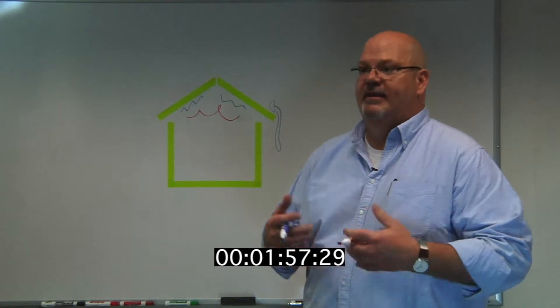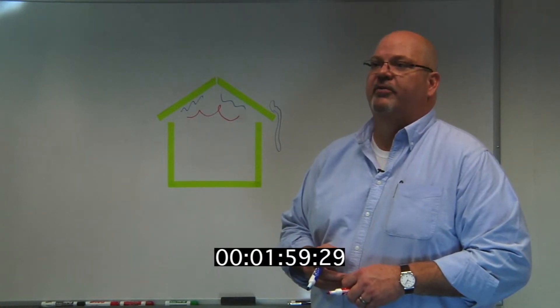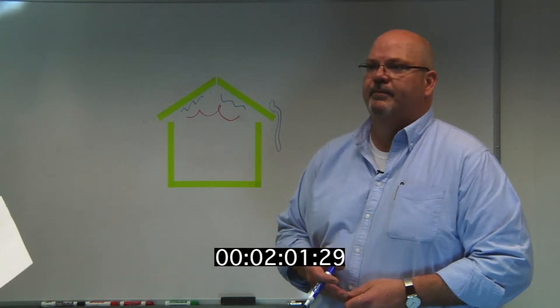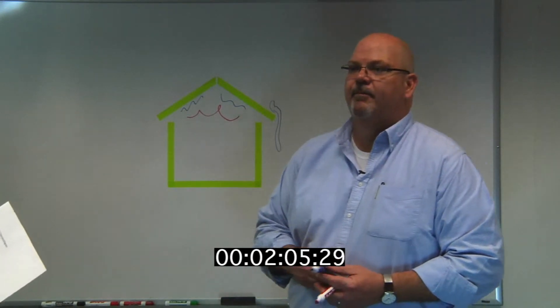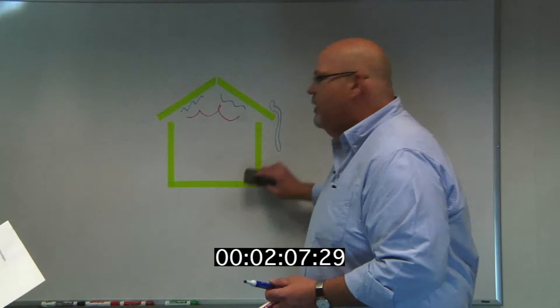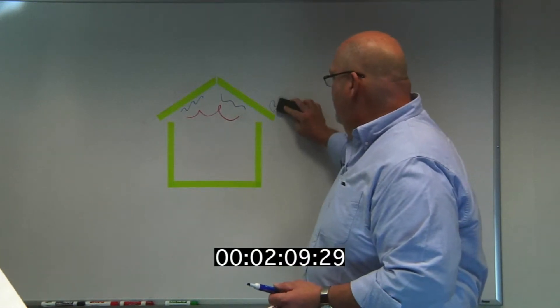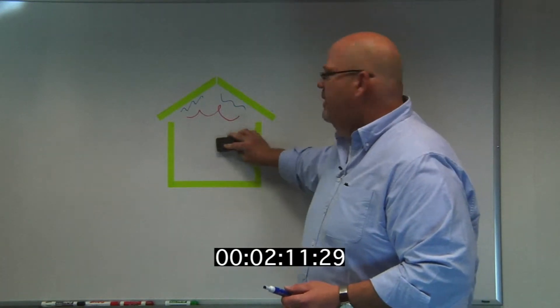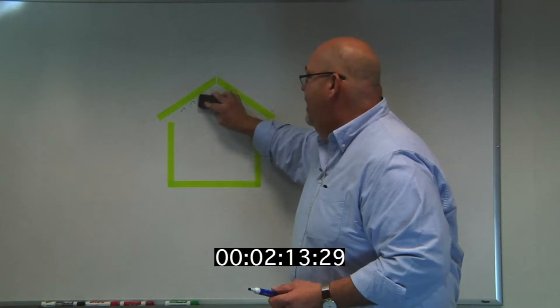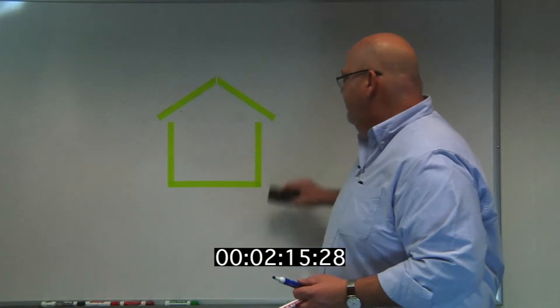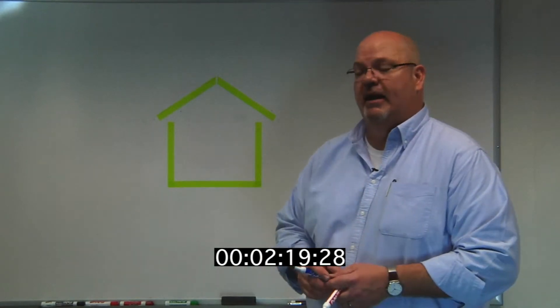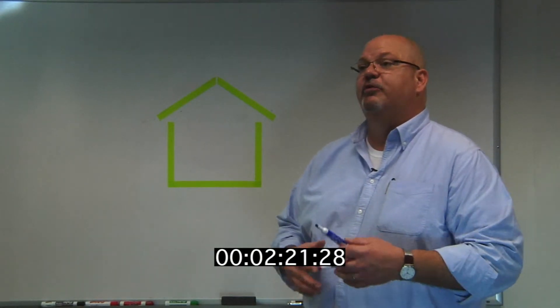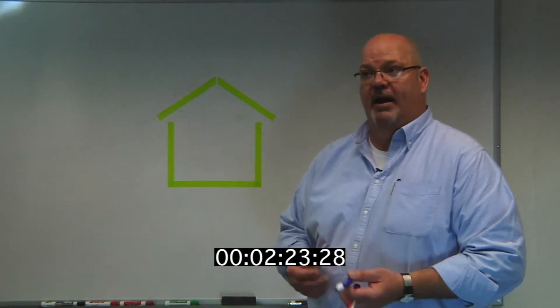I understand that we want to go for natural ventilation. Can you tell me a bit about natural ventilation and how the simplicity of it protects you? Sure. Natural ventilation occurs principally by taking advantage of some forces that are going to be working on the house every day. The two principal effects which move the air through the attic by natural ventilation are the stack effect and the wind effect.